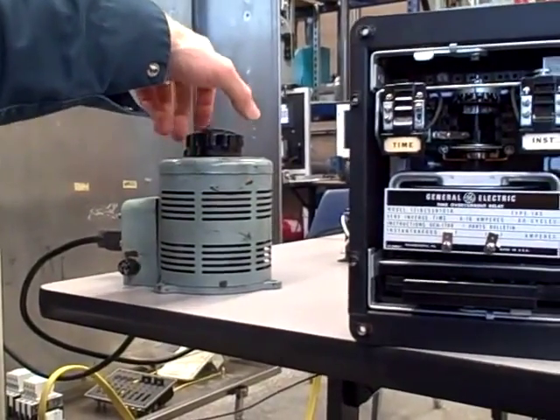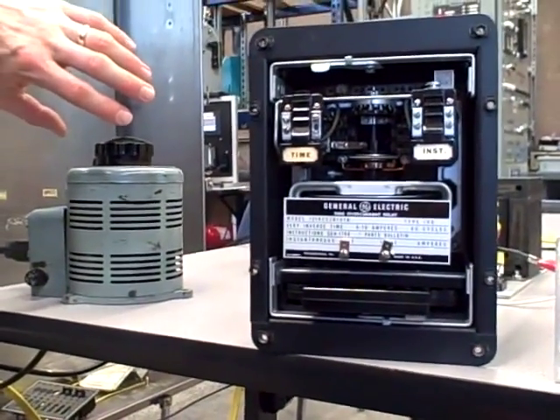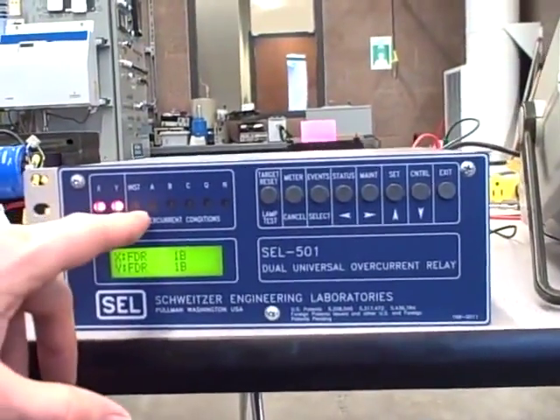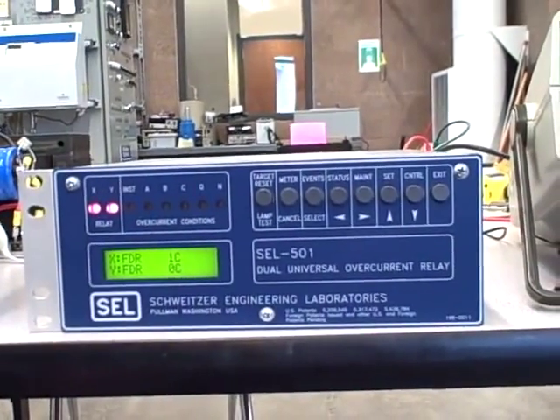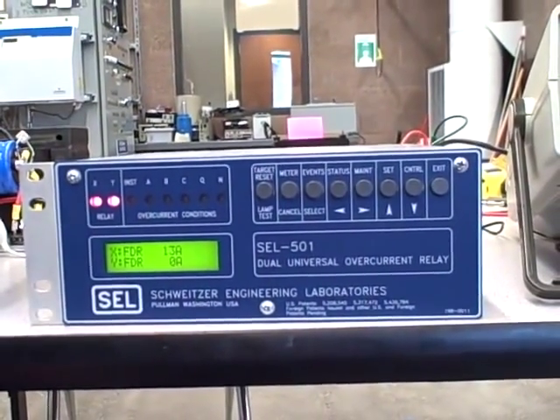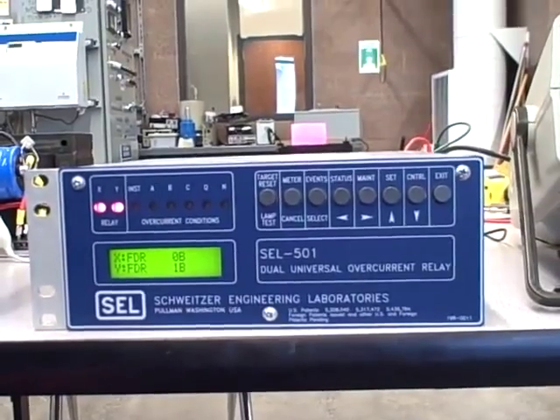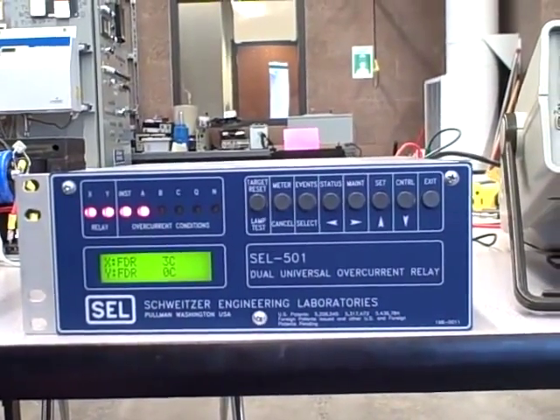I'm going to very quickly turn it up, and so what that will do is provide an even stronger amount of current than we had before going to the relay. And now it's going to be programmed to trip on instantaneous overcurrent. This is where it exceeds a threshold that trips immediately without waiting and without timing. So here we go. And we get an instantaneous trip.